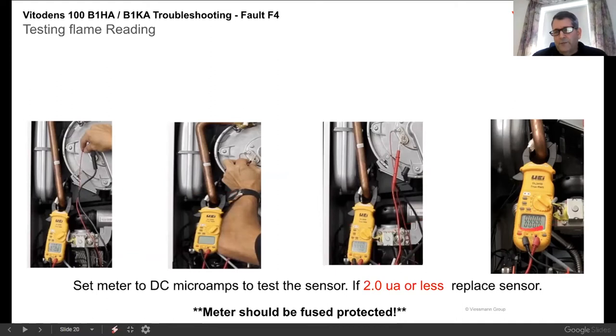Normally, during changing out pitches here, I lost the reading, but I actually had a 3.5 reading on this here, which was telling me that I was above the 2.0 that they say in the manual. So my flame sensor was good on this one here, so I could continue on with my test.